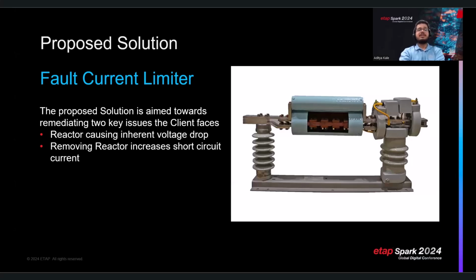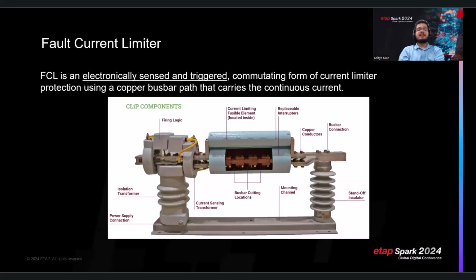Before we jump into the ETAP demo, let's take a moment to understand the FCL. The FCL is an electronically triggered current limiter that operates by sensing and quickly interrupting fault currents before they can cause damage. Here are a few key components of the FCL: the current transformer inputs that sense the current levels, the copper bus bar which carries the normal operational current. Positioned above the bus bar is a fusible element ready to respond in the event of a fault. The entire operation is managed by the firing logic, which controls the pyrotechnic actions of the limiter, which requires an external power source.